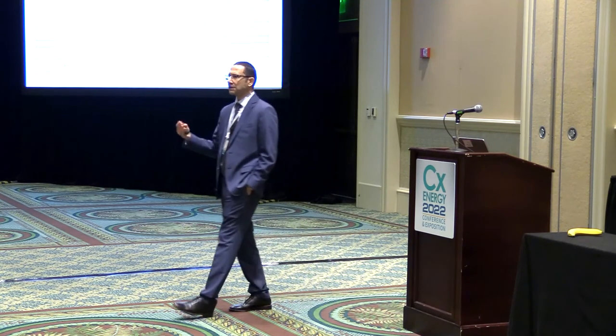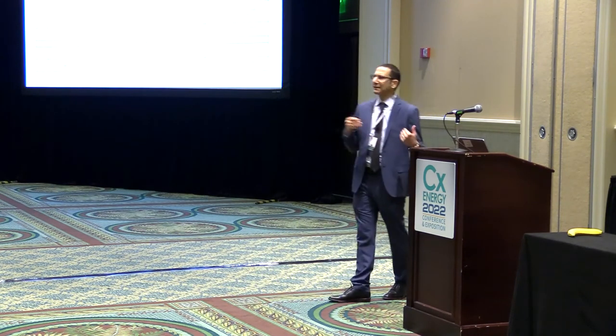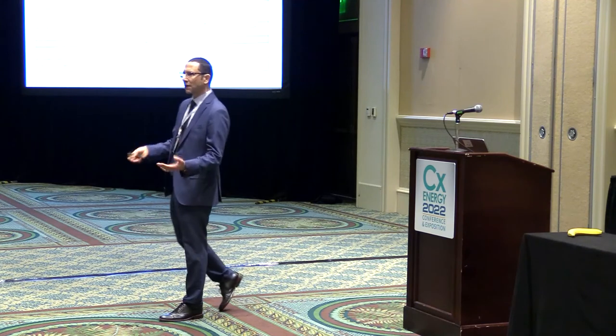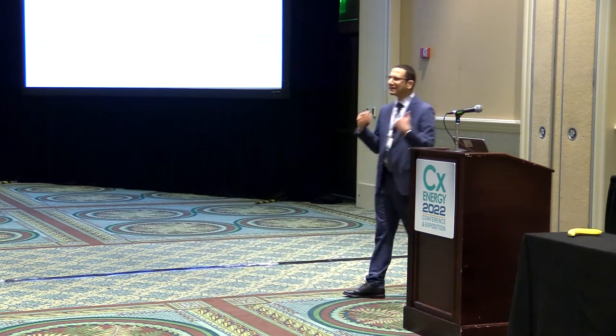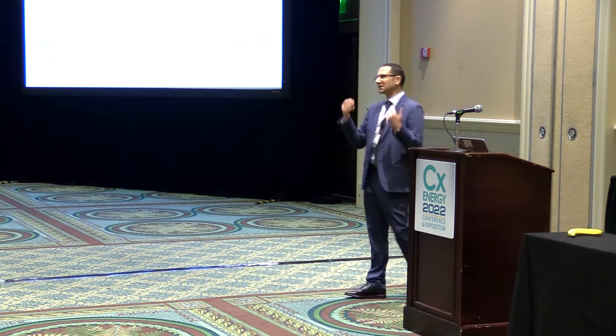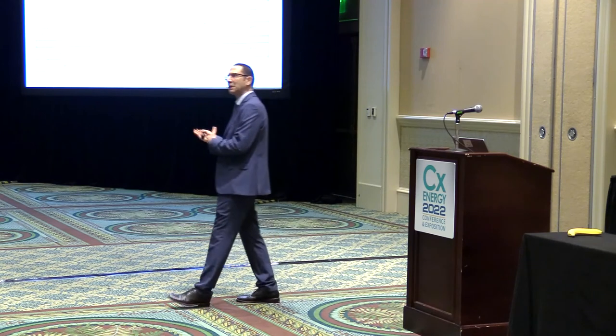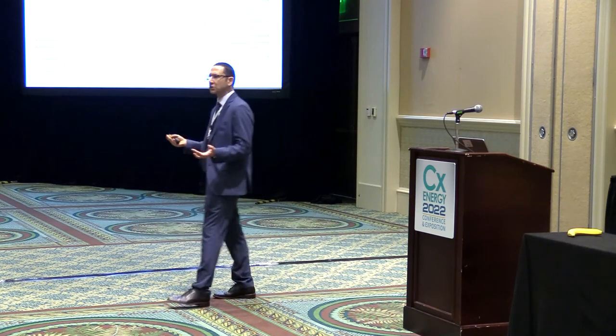The assessment is what's important to me, this is where I make all my decisions - going there, understanding the systems. The only thing drawings give me is the data for air handlers, understanding their capacity. But typically, if you're doing an assessment with boots on the ground, you're able to take all the nameplate data and gather a lot of that information. At the end of the day, that's all I need, because I'm in the space, looking at the air handler, the installation, the central plant, how it's installed, how it's running.